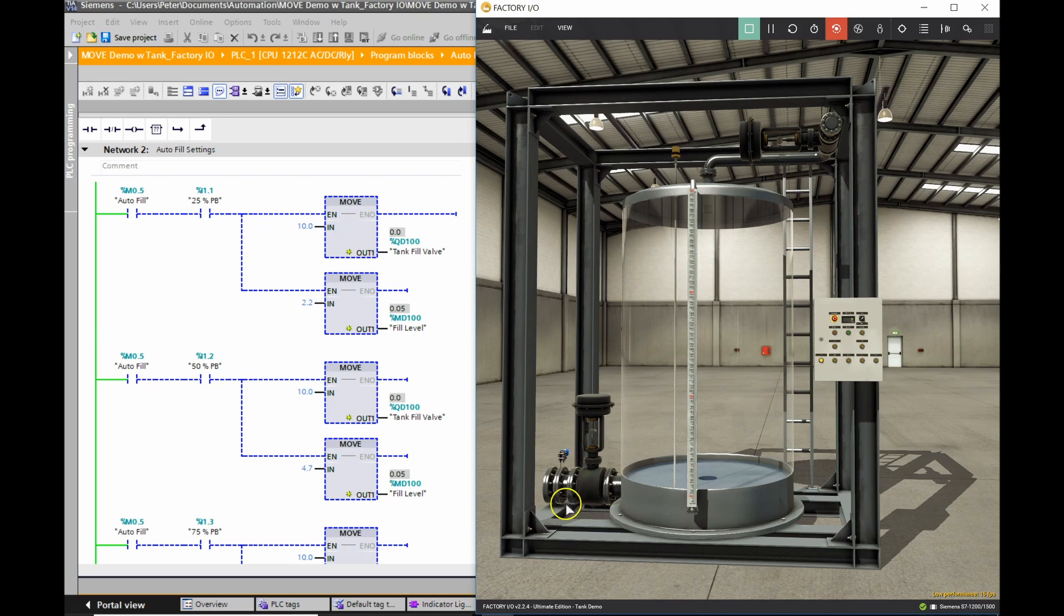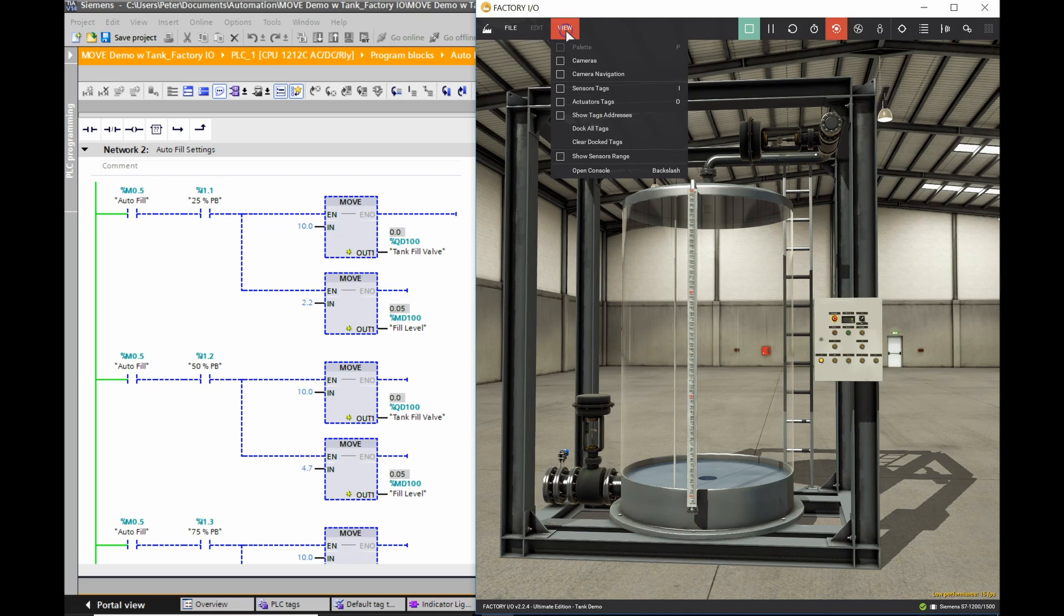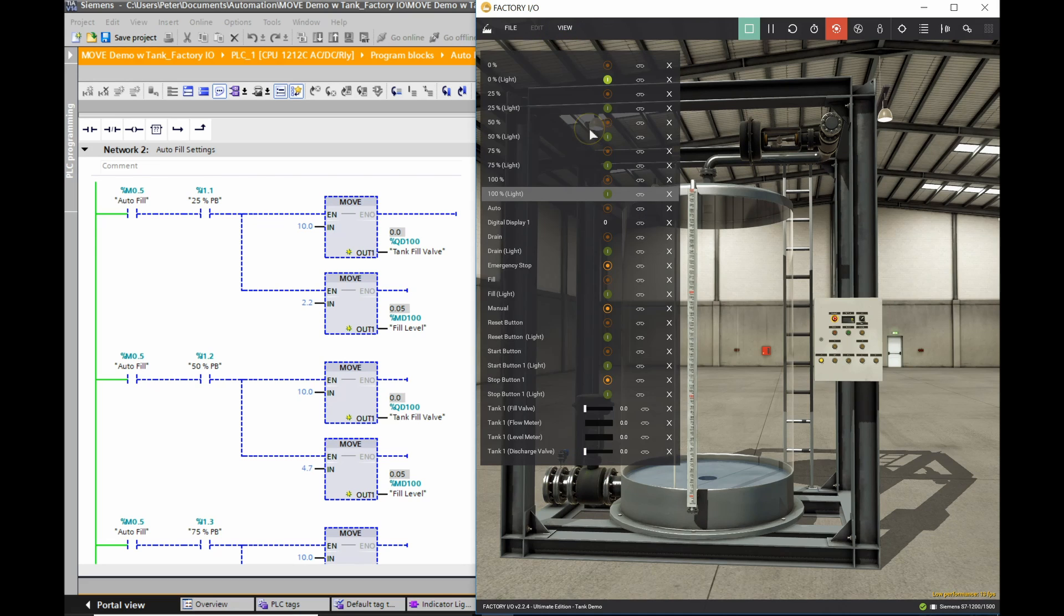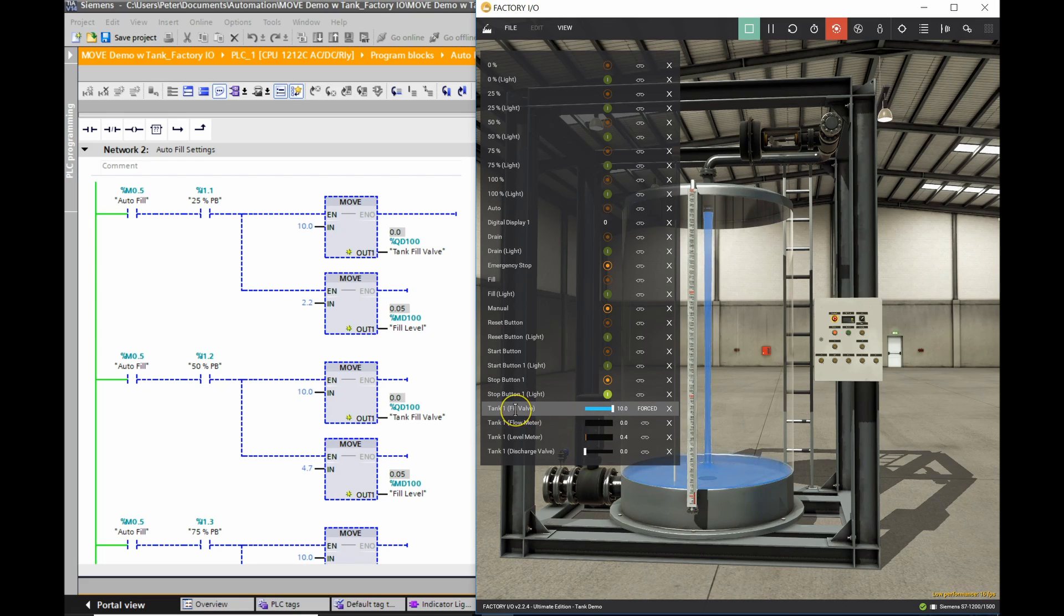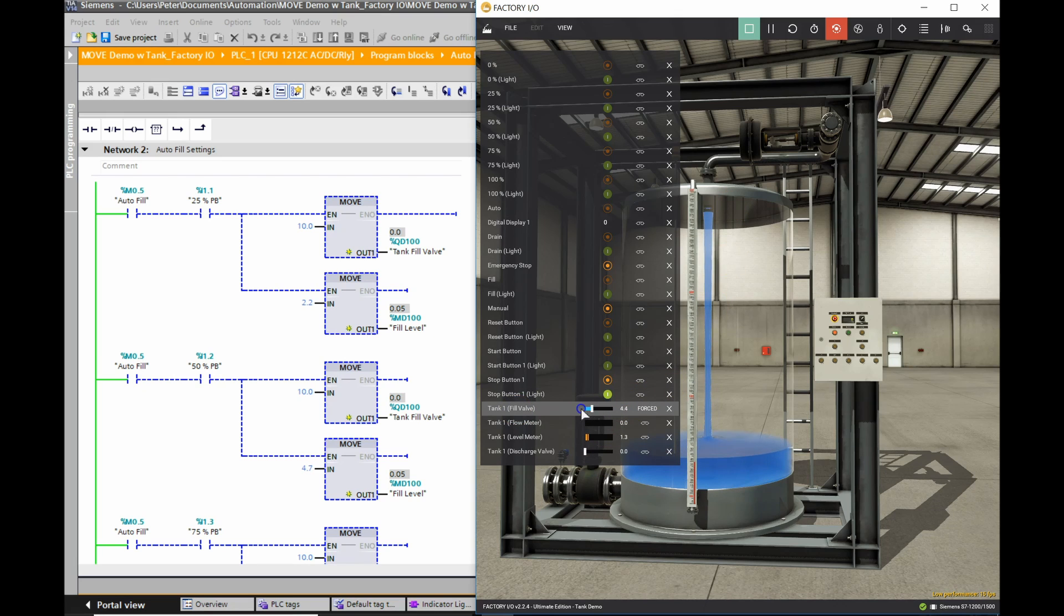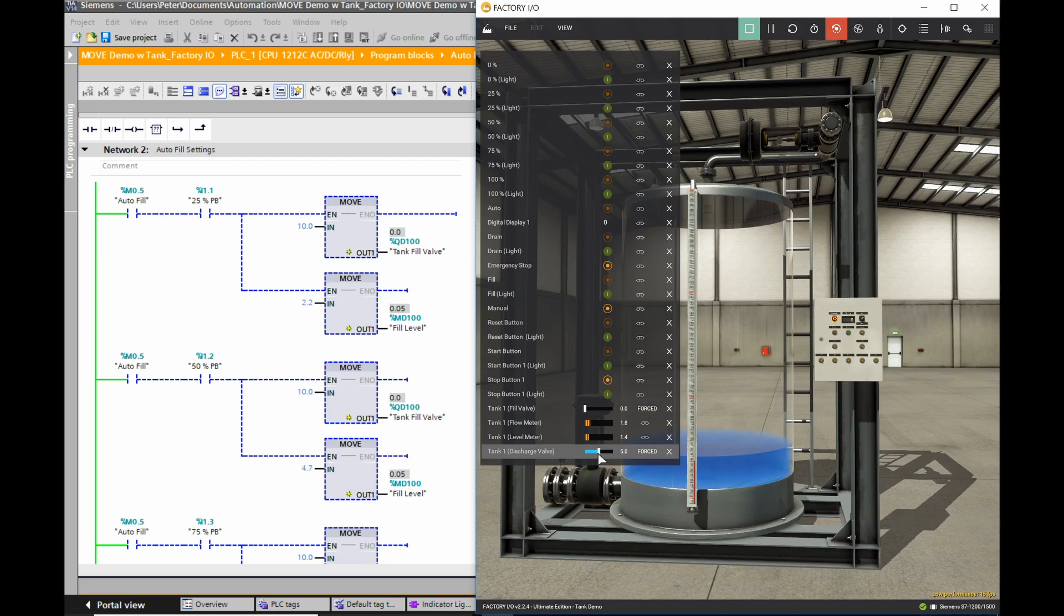What you need to know is that these two valves, the fill valve and the discharge valve, are proportional valves. If I put a zero to ten volt signal to my fill valve, it's obviously going to turn it on. If I put five volts to my discharge valve, I've got it halfway open. At ten volts I'm fully open now.